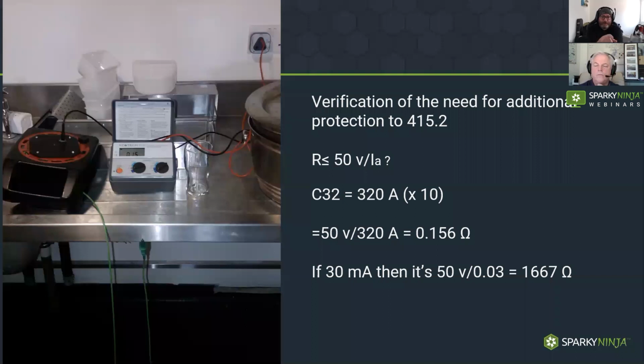So I did this measurement here. This is on a socket outlet circuit on a C32, so times 10 for the current that could flow, maximum for the minimum for the duration of 0.1 seconds, 320, the C-type multiplier. I got 0.156 by calculation with Ohm's law, and I measured 0.15, so that's bang on the money.